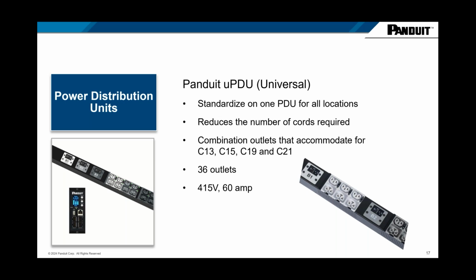What's being shown is a set of combination outlets. Again, not sure what's going to be thrown your way, so we can accommodate all different plug types, C13, 15, 19, 21. In this case it's 36 outlets. We're seeing definitely a demand for 415 volt and 60 amp, and there's also an appetite to go beyond 60 amp, into the 100 amp range, to support these AI deployments.